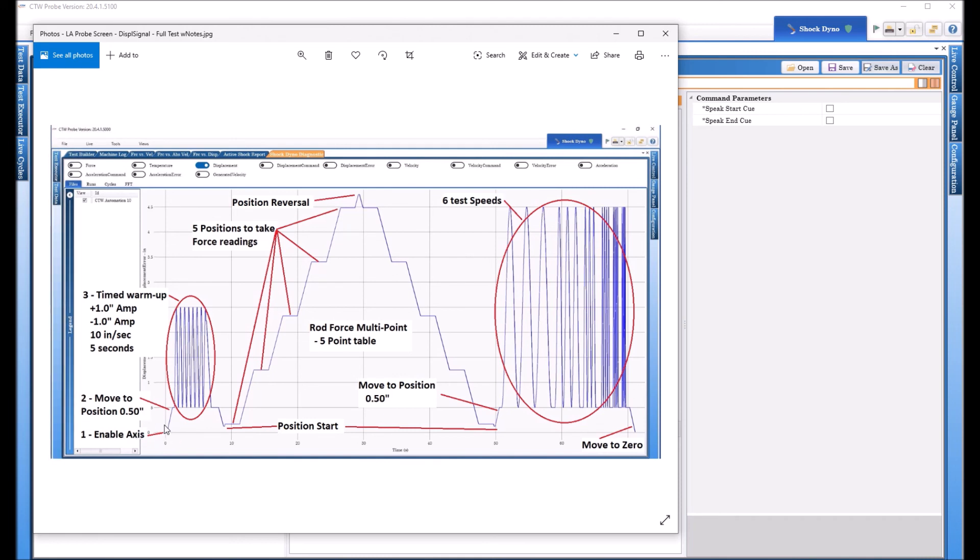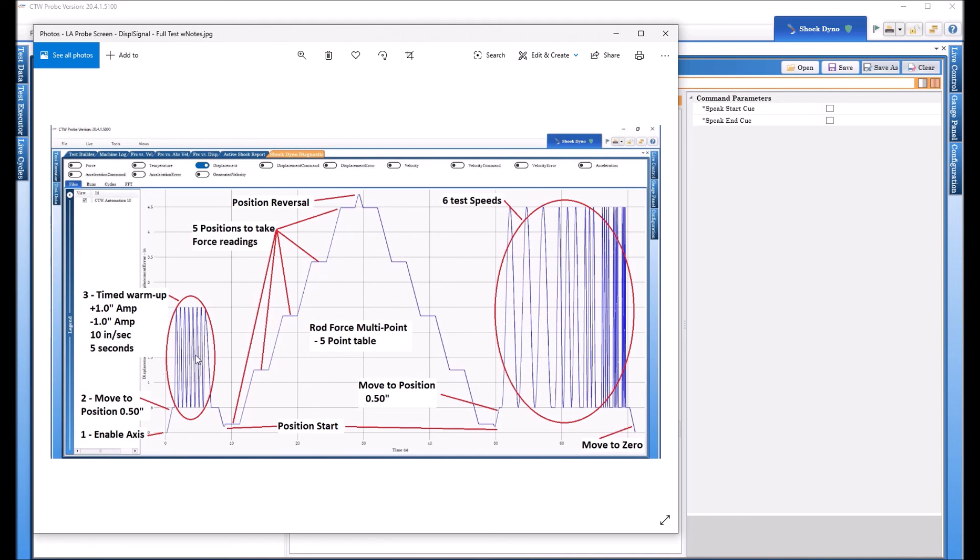So turn the axis on and this you can find this in our new manual. I've gone through and tried to do everything in the new manual word by word page by page picture by picture so that you can read it slower but we all know nobody looks at the manual so that's why we're making videos. So you turn the axis on and you move to position I moved up a half an inch and then I said do a timed warm up.